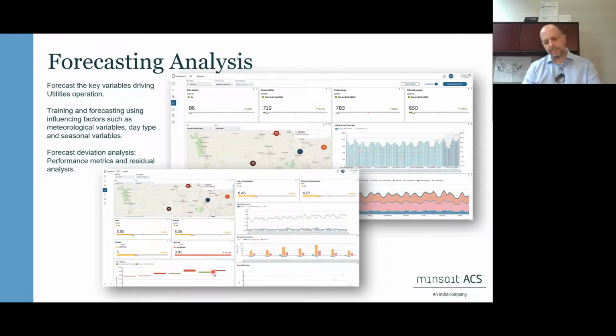We also have an internal system to control the error once the forecast algorithm forecasts the load. Of course, if we see that this error is constantly increasing, then we can retrain the algorithm to reduce the error compared to the real measurements. Having the hourly load 24 hours ahead becomes very important. It is very important information for the control center to organize switching, for example. If you use that information together with your most loaded feeder, then you will know, for example, that you want to divert part of the energy flow into other feeders that are less loaded than the very loaded ones. All this information can be given 24 hours ahead up to 1 week ahead. The further away we go in time, of course, the less precise the forecast will be, and as the date gets closer, it will be more precise.